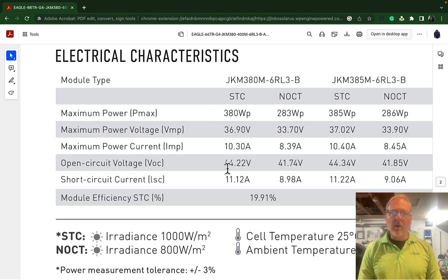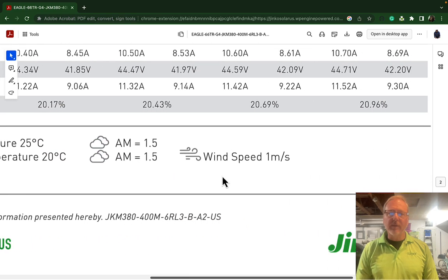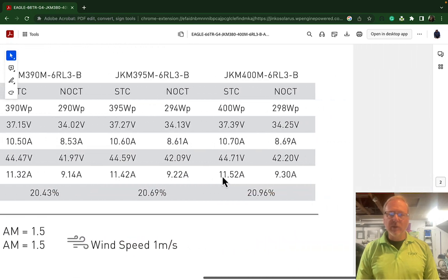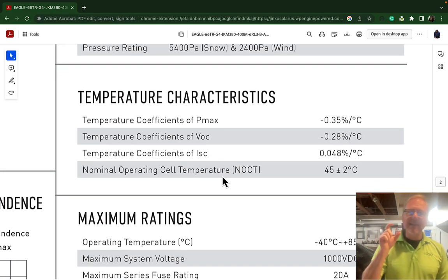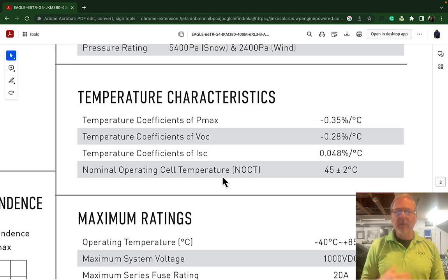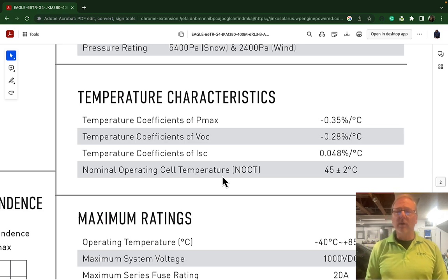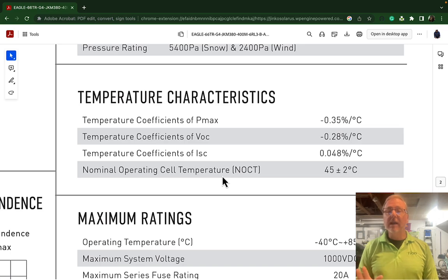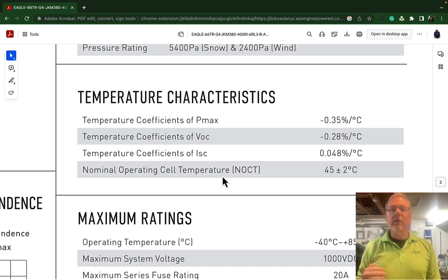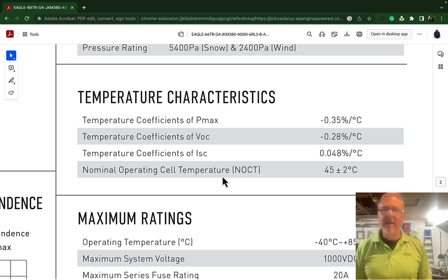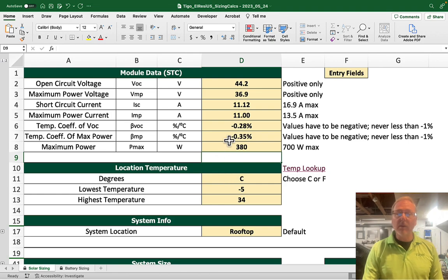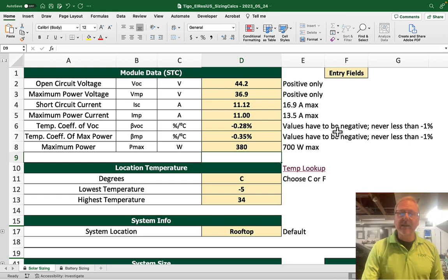This is all the information that we needed. The temperature coefficients are right here. When you go to the temperature characteristics section, you will find all of those. The temperature coefficients of either max power or open circuit voltage — they're always negative, because they have an inverse relationship to temperature. In other words, as temperature goes up, Pmax and VOC go down. That's why they're negative, and they must be entered as a negative number here — never less than 1% and it has to be negative.